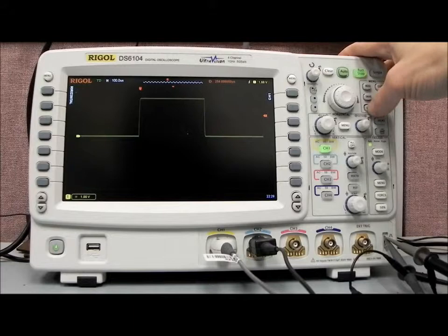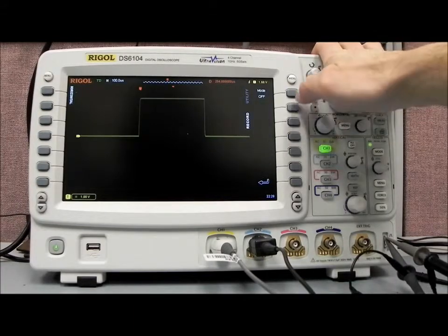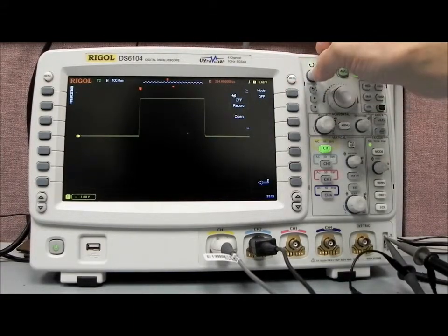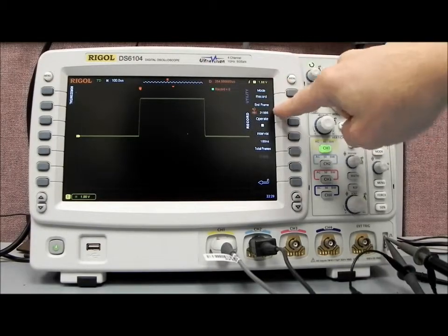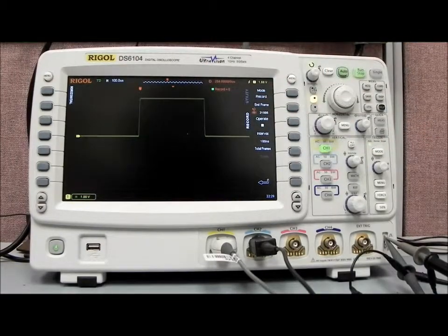So to get to record, we're going to press Utility, open up the record menu, and then let's enable record. And you'll see that now we have 31,986 end frames, or that is our end frame. You can basically think about a frame as a bitmap image of the displayed values on the screen, and the number of frames that we have is directly corresponding to how much data we're going to collect per frame. If you're going to have a very large data set per frame, we're going to have a limited number of frames. If you want to have more frames, you're going to want to collect less data.